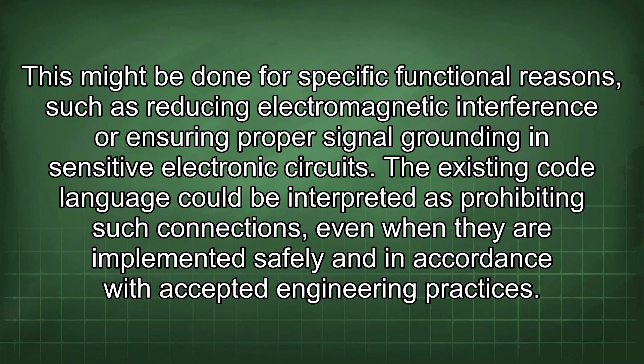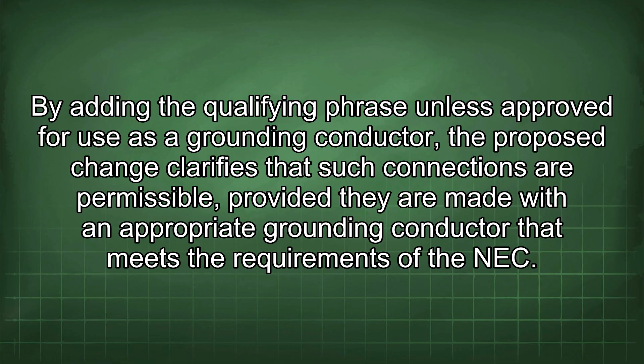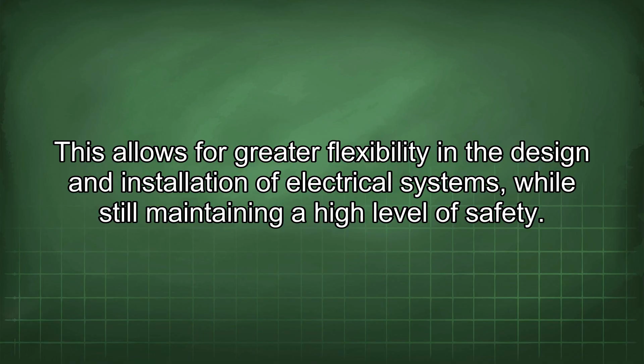By adding the qualifying phrase 'unless approved for use as a grounding conductor,' the proposed change clarifies that such connections are permissible, provided they are made with an appropriate grounding conductor that meets the requirements of the NEC. This allows for greater flexibility in the design and installation of electrical systems, while still maintaining a high level of safety.